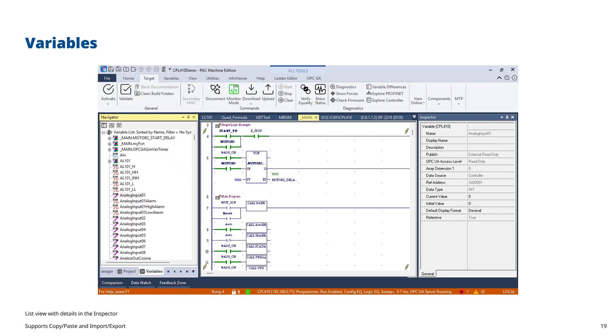And here's the data watch window. So again, I've got the Navigator open, I've selected a variable, and then you can see that variable in the data watch using the auto tab, or in this case, I've actually created a data watch by dragging and dropping from the Navigator. I've dragged and dropped the variable names I want to see into the data watch, into the static view. So in this case, I can see the analog input itself. I can also see the overall alarm value, and I've got a high alarm and a low alarm. So you can see there's the address for the analog input 01, because that one is a mapped variable.